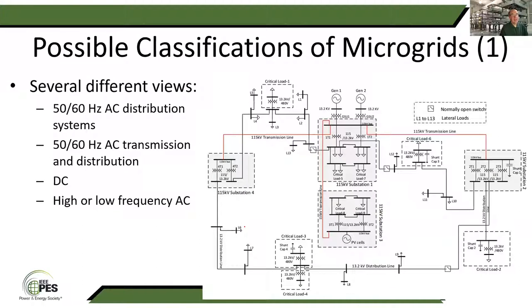And so when you start classifying microgrids, you could classify them as AC distribution systems, so 50 or 60 hertz systems, depending on where you are in the world. And that's the most common definition of microgrids, is people generally look at this as a system that's a fundamental frequency distribution system. Another option is things that have a mix of transmission and distribution systems. So this is a system that we were involved with studying for a utility that has a mix of transmission systems and distribution systems. And they basically had a prioritized set of loads that they wanted to be able to support with the set of generators that they had.